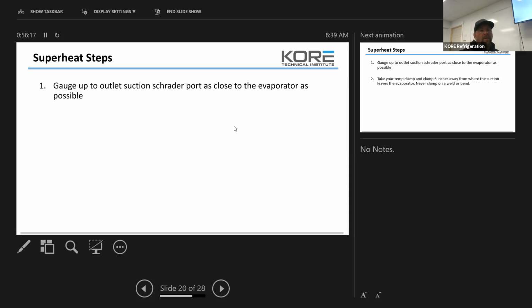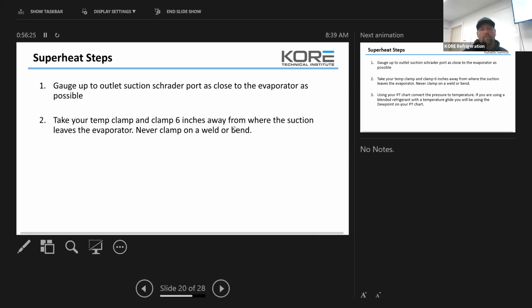Gauge up to the suction service port. So let's talk about the superheat steps. First, you're going to take your stubbies and gauge up to the port. Second, you're going to take your temp clamp. If you guys don't have a temp clamp, buy one today.